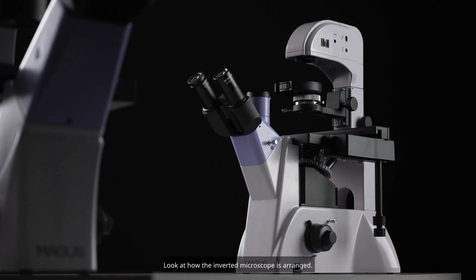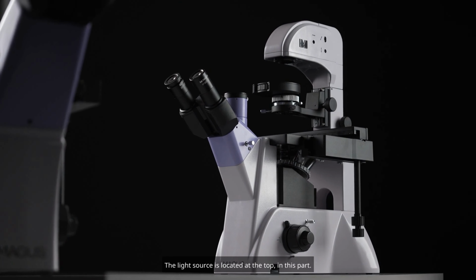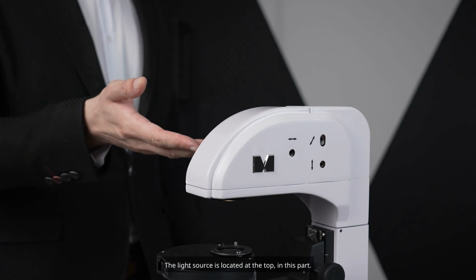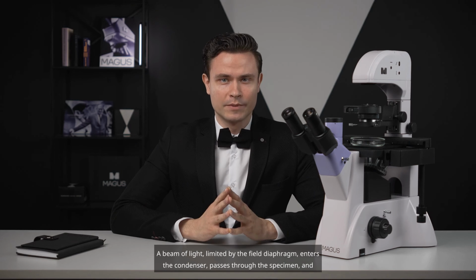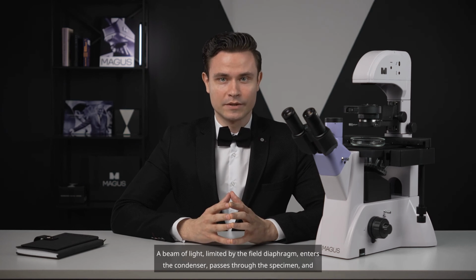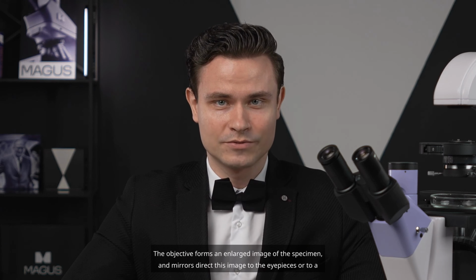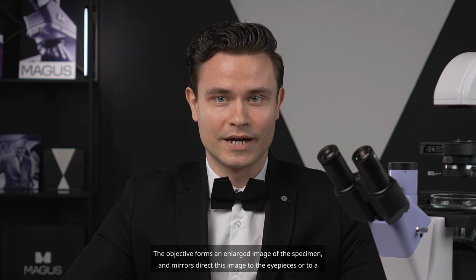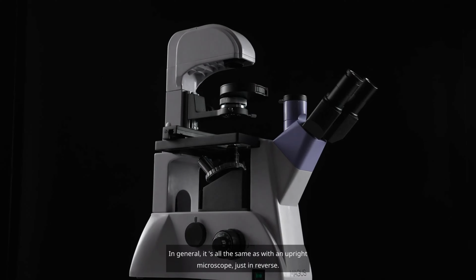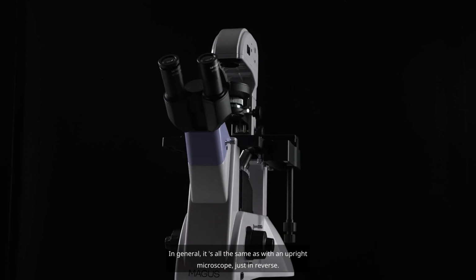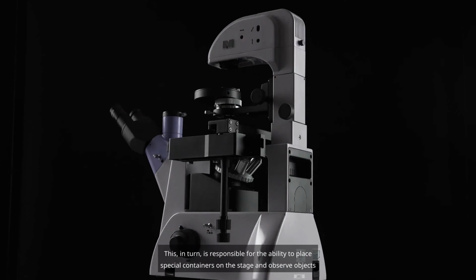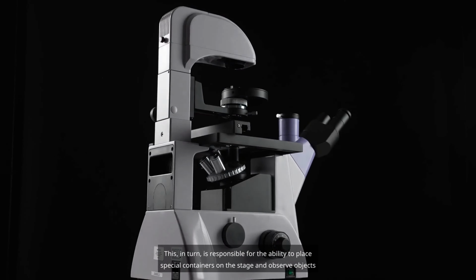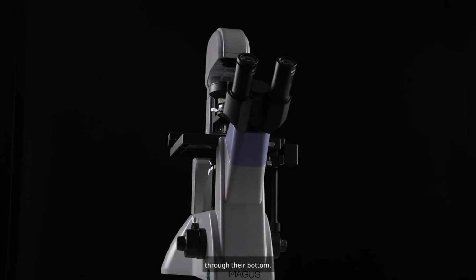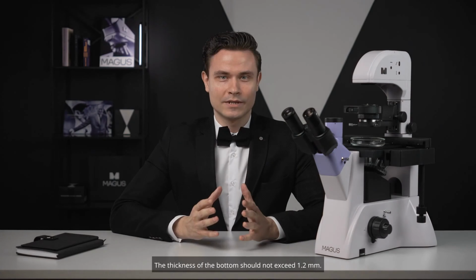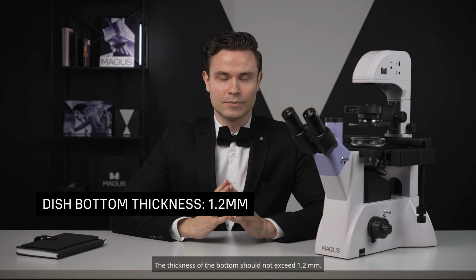Look at how the inverted microscope is arranged. The light source is located at the top, in this part. A beam of light, limited by the field diaphragm, enters the condenser, passes through the specimen, and reaches the objective. The objective forms an enlarged image of the specimen, and mirrors direct this image to the eyepieces or to a digital camera. In general, it's all the same as with an upright microscope, just in reverse. This, in turn, is responsible for the ability to place special containers on the stage and observe objects through their bottom. The thickness of the bottom should not exceed 1.2 millimeters.